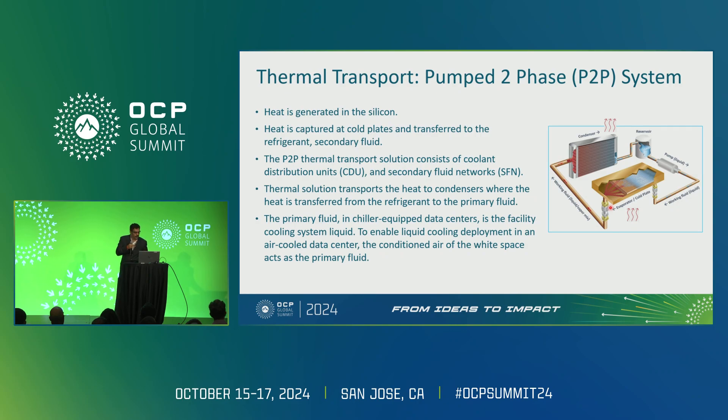When the mixture goes to the condenser, it could be an air-cooled condenser for sidecar operation in an air-cooled data center, or you can take the heat outside directly in edge data centers using ambient air. If you use a liquid-to-liquid configuration, you can bring very warm water cooling. For example, one application can cool kilowatts of processor using 55°C incoming refrigerant with facility water at 48°C, even on a 200 kW system, and this can be expanded to 400 kW and beyond for heat reuse.